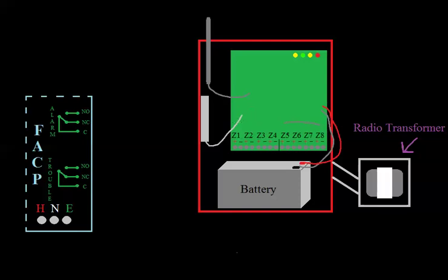And you could buy these radios in a few different configurations, but the most common configuration is zones 1, 2, 3, and 4 usually work like our digital dialer. They work like a mini fire alarm panel. They are looking for an end-of-line resistor. If they get an open, they will send a signal. If they get a short, they will send a signal. And you can actually program the central receiver to interpret. I could program it so that an open will be a fire alarm. I could do anything I want. But for the most part, it's going to send a data packet just like our dialer did.